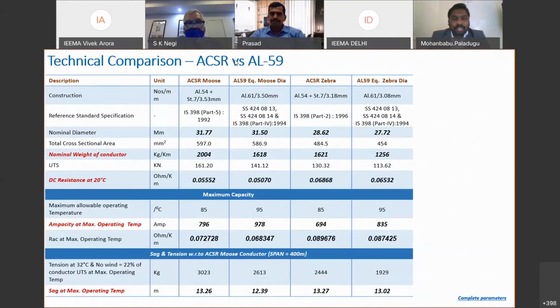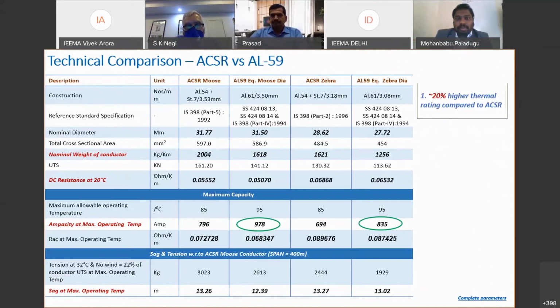So from this point, I will touch upon what we have already seen in Negi sir's earlier presentation, a technical parameter comparison of ACSR versus AL59 at Moose equivalent and Zebra equivalent. For any conductor selection, the major criterion first is the power carrying capacity, or the thermal rating of the line. In India, we generally plan a transmission system with a contingency for reliability purposes. It is known to everyone that the loading of the line under normal operating conditions is generally around 50% of its thermal rating. This is one point we should note when we are talking about these parameters. And under any contingency, as the planning criteria says, without any shutdown of load or any disturbance in the grid, I should be able to carry full capacity or full load.